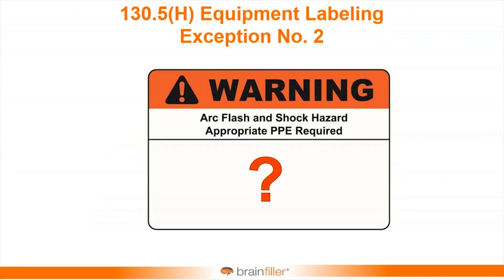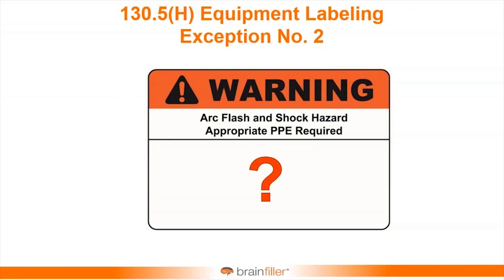I know this flies in the face of what we're used to, but what you can do is reference the department, the group, or the person that has the report — the arc flash study. You look at what configuration you're in right now, consult the report, and dress and protect yourself based on the mode you're actually operating under. Instead of multiple labels or worst case, this is a method. You don't have to do this — it's just an option given as an exception in 130.5H for equipment labeling.